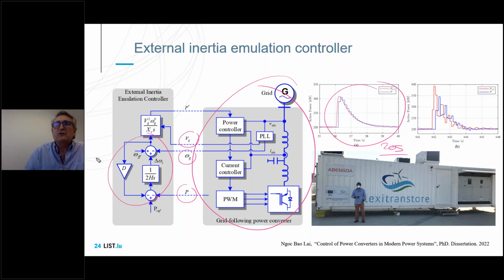Based on that, we can calculate the swing equation and determine what should be the power reference for emulating such an inertia externally in a conventional grid following converter, the one you can buy for a PV panel, which is really cheap, PV panel or PV plant.